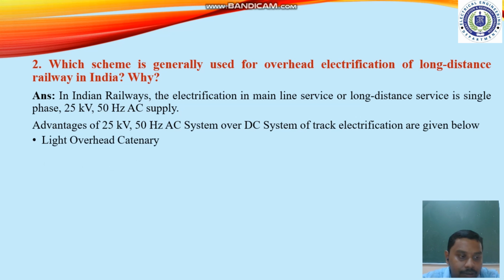The first advantage is a light overhead catenary. Since we use 25 kV voltage, the line current is less, which reduces the cross-sectional area of the overhead conductor. So a small size conductor can be used, and the supporting structures and foundations are also light and simple. That's why we get a light overhead catenary.